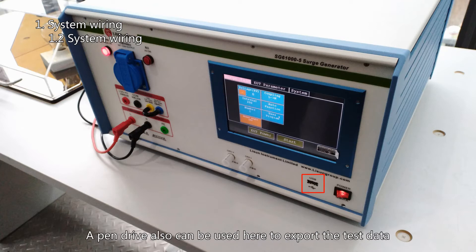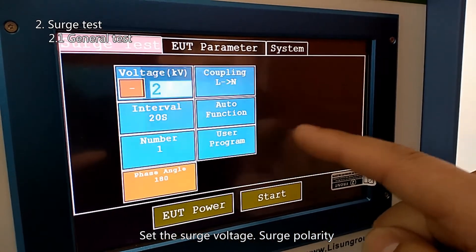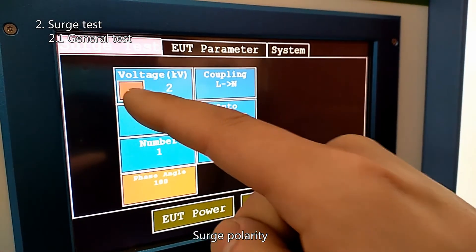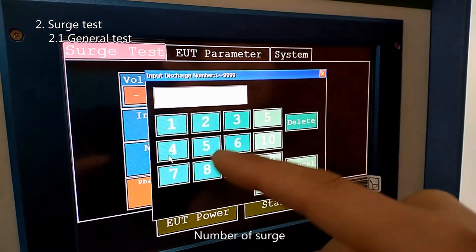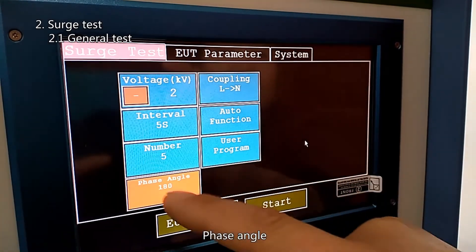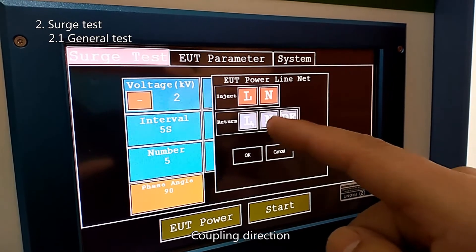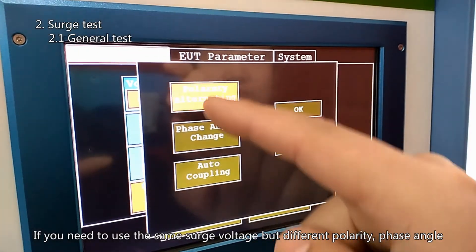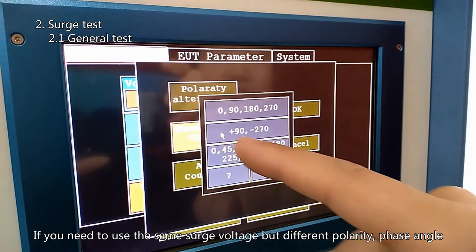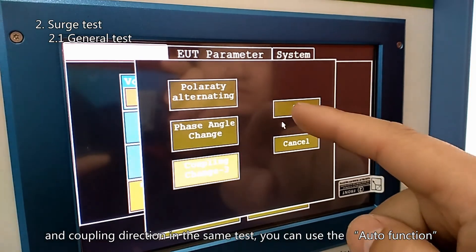A pen drive can be used here to export test data. Set the surge voltage, surge polarity, surge interval, number of surges, phase angle, and coupling direction. If you need to use the same surge voltage but different polarity, phase angle, and coupling direction in the same test, you can use the auto function.